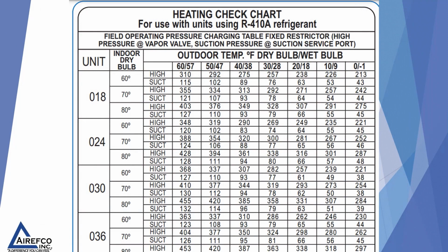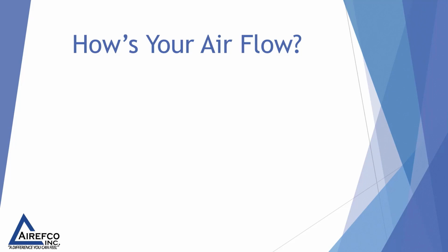All major manufacturers will give you a check chart for the different refrigerants and the different units, which will give you a ballpark figure for temperatures and the size of the unit as to what high and low side pressures you should be reading if the system is operating correctly. One of the main questions that we in the tech support group ask all the time to techs is, how's your airflow? And of course the answer that we always get is, it's good.